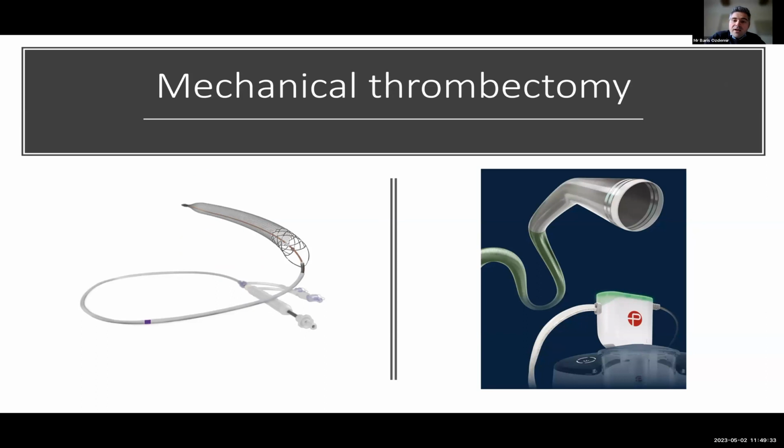We now have more sophisticated devices that can remove thrombus. So what you see on screen left is called the ClotTriever, and it has an element that cores out the thrombus and then a collection basket above it, which you can see here. And this allows us to remove all the thrombus in a single session. And I'll show you later on in the presentation the sort of thrombus that comes out.